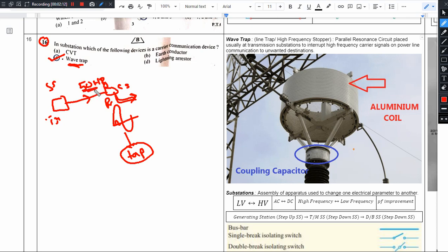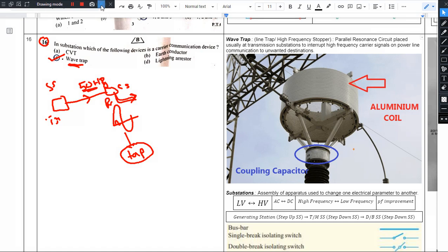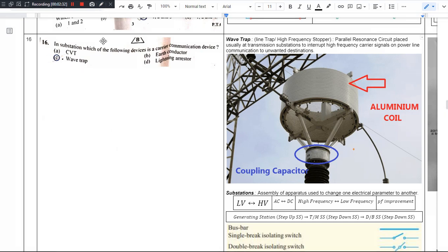Since we cannot use 50 Hz for communication, we use a higher frequency — kilohertz, megahertz, or gigahertz — and we trap it so that the communication signal does not cross to the next substation. So the answer to this question is wave trap.